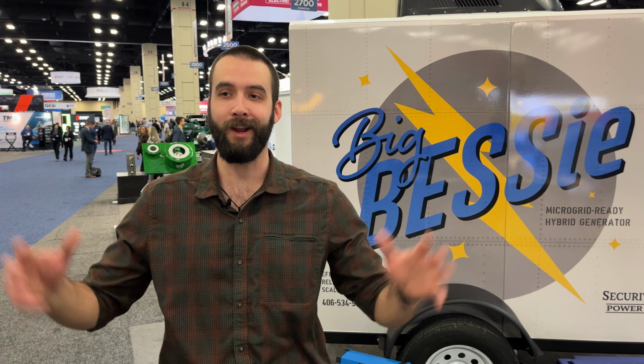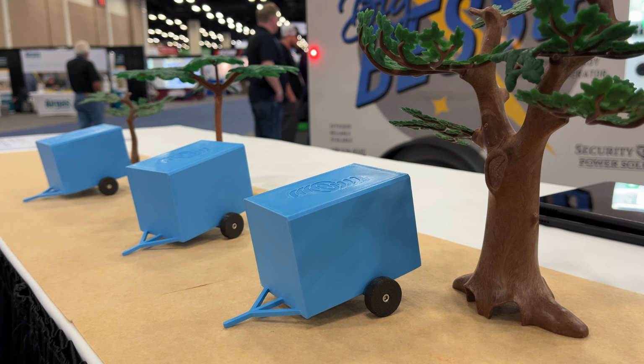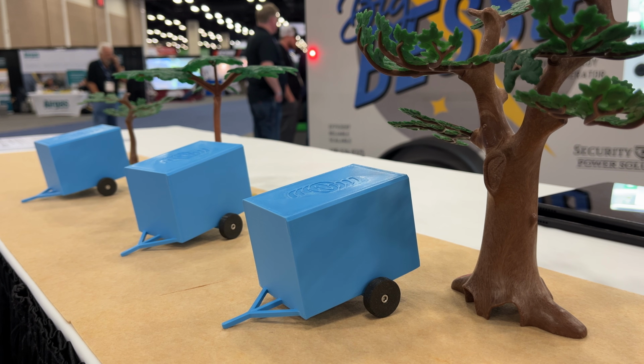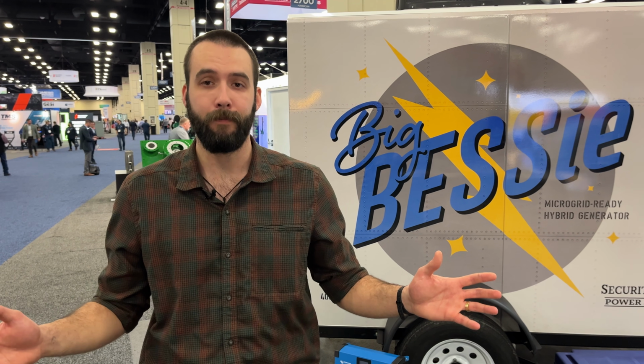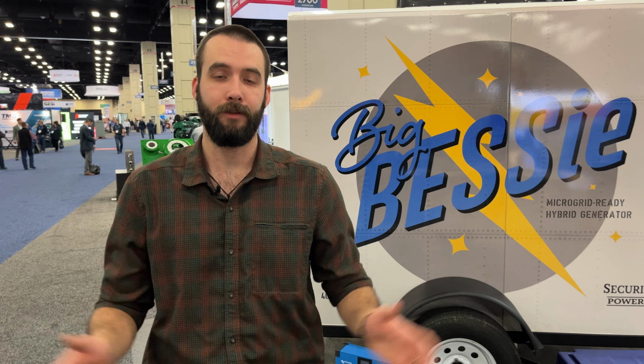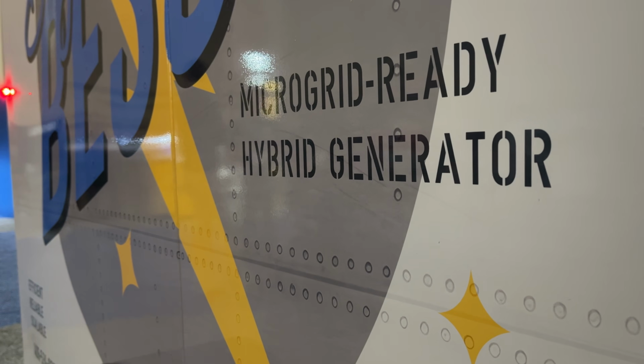Victron is excited with the introduction of this trailer to introduce their microgrid functionality. Microgrid functionality is advanced AC coupling on the AC output of the Victron inverters using hybrid droop to really just synchronize with multiple other units paralleled on the AC bus. This allows a Victron power system to keep a safe, low voltage 48 volt DC bus internally and then scale infinitely on the AC output side of things to handle whatever load the job site or application might throw at it. So that's the idea behind the Big BESSie.